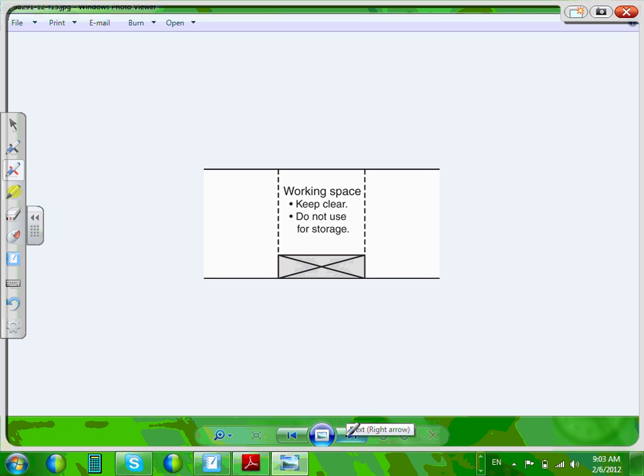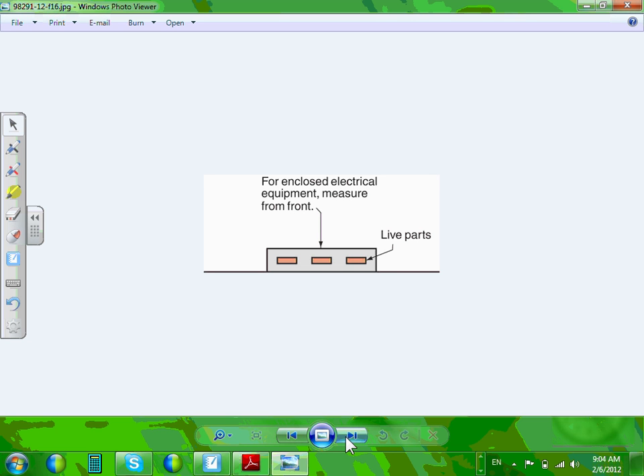If the contractor walks in and the inspector sees this one here, he will ask you to remove it, because that space is dedicated for a person to work on the electrical equipment safely. So use your judgment. When we tour these data centers, you're going to see how clean they are. All the switchgears, no junk in front of them. And other places I've been, you can't get to the panel. So by code, you can't use it as storage. You have to keep it clear of all obstacles. Okay, so moving on.